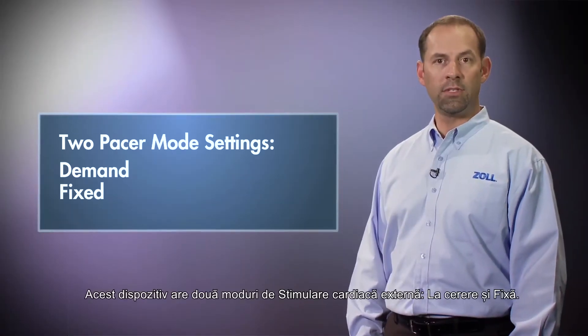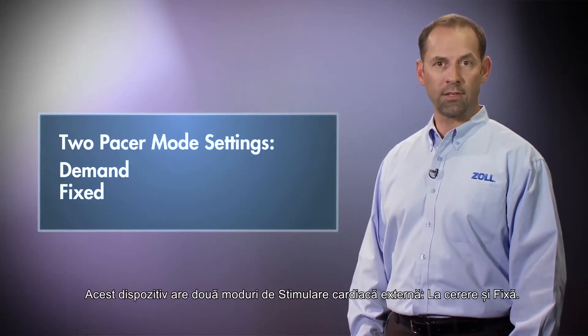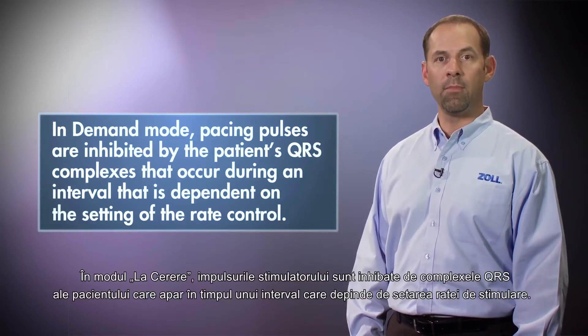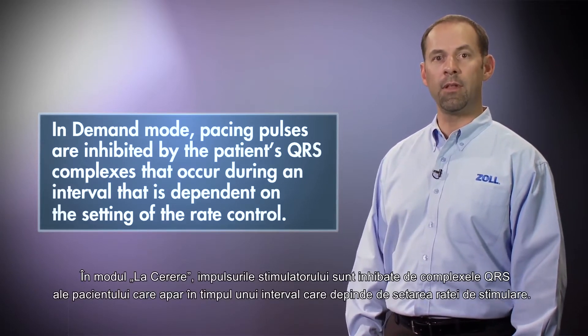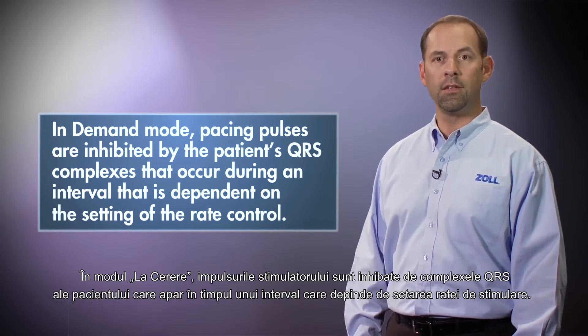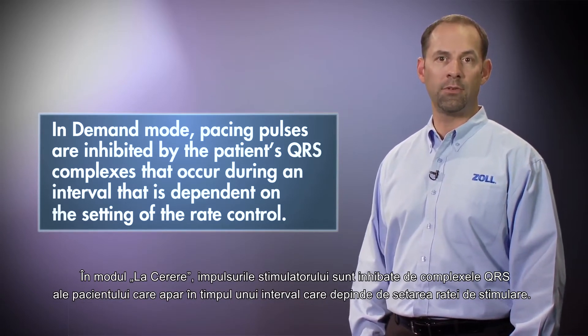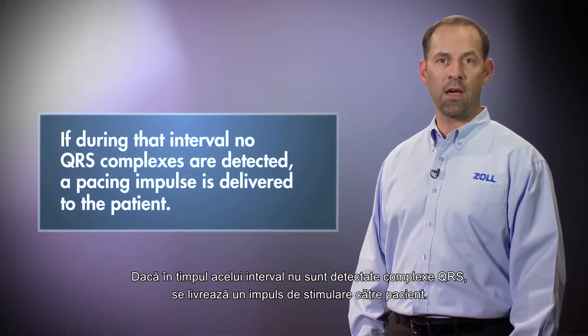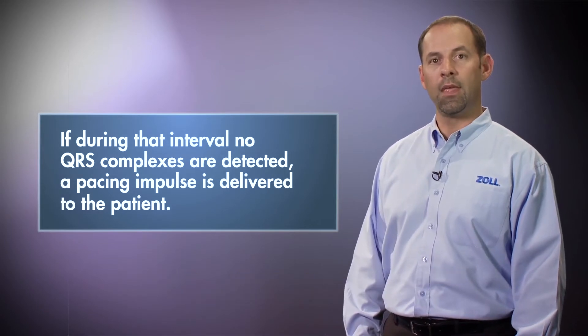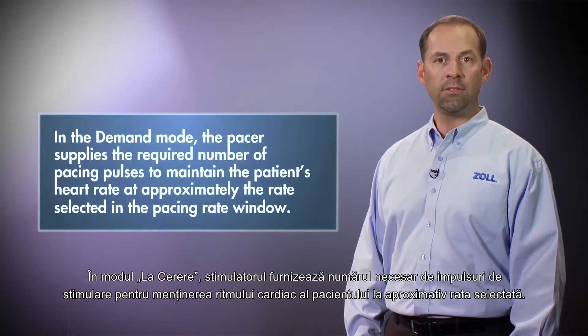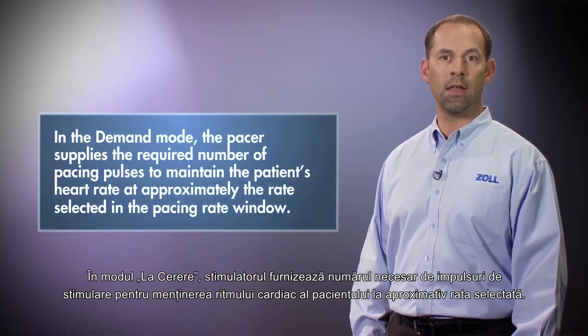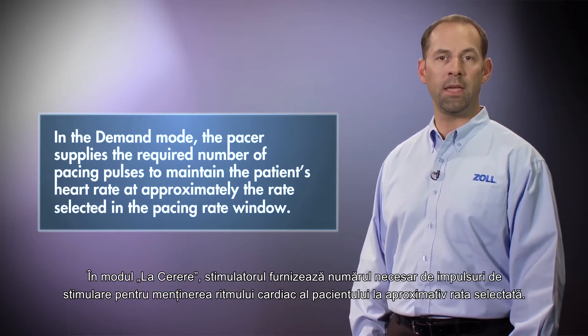This device has two pacer mode settings: demand and fixed. The factory default mode setting is demand. In demand mode, pacing pulses are inhibited by the patient's QRS complexes that occur during an interval dependent on the setting of the rate control. If during that interval no QRS complexes are detected, a pacing impulse is delivered to the patient. The pacer supplies the required number of pacing pulses to maintain the patient's heart rate at approximately the rate selected in the pacing rate window.